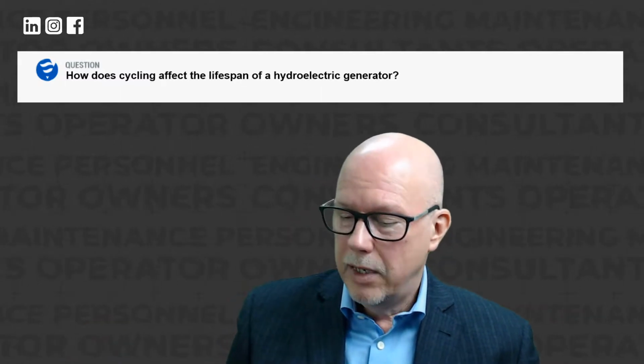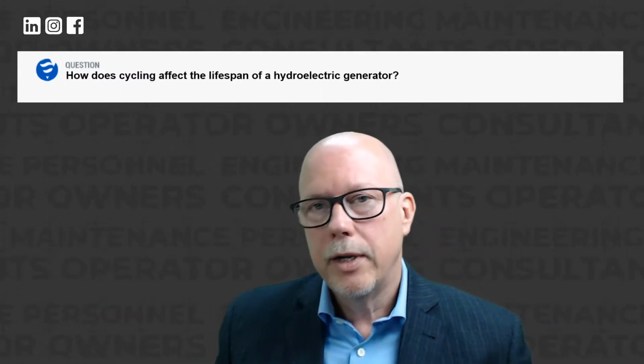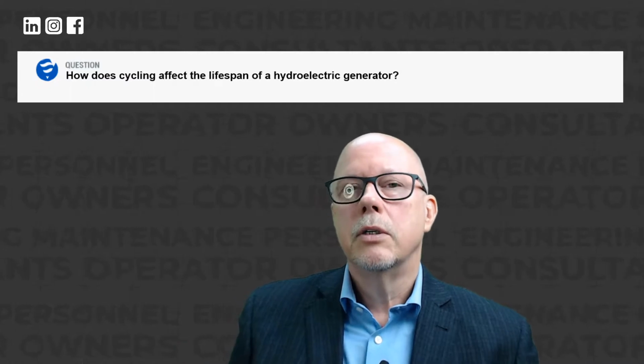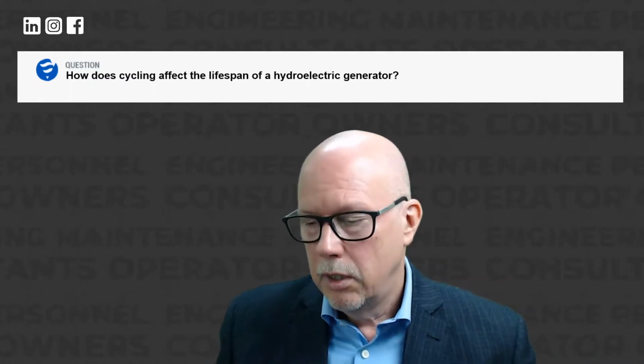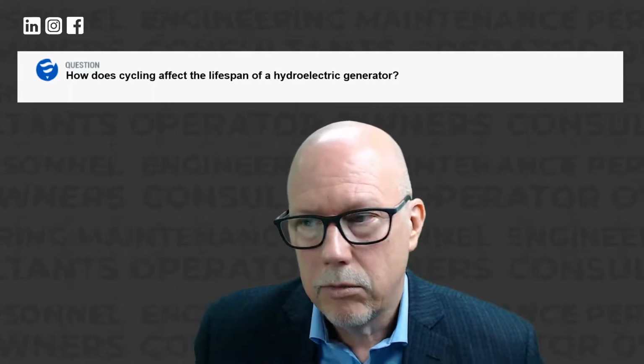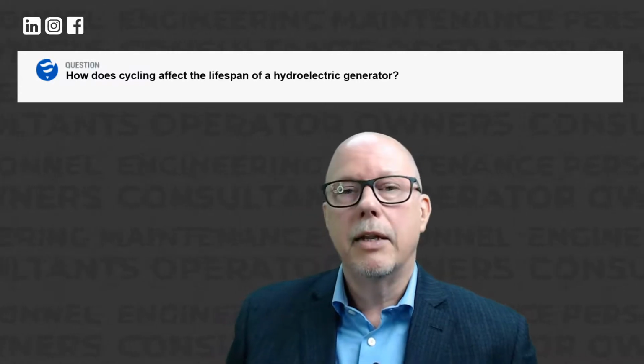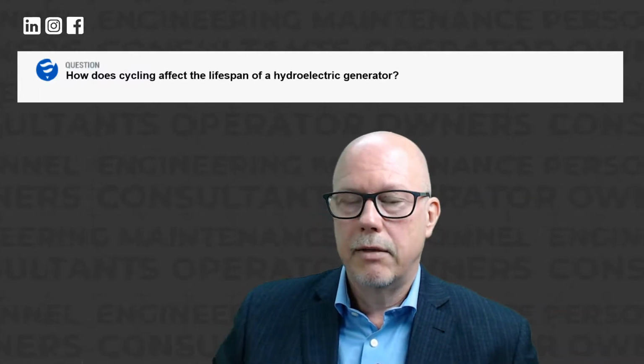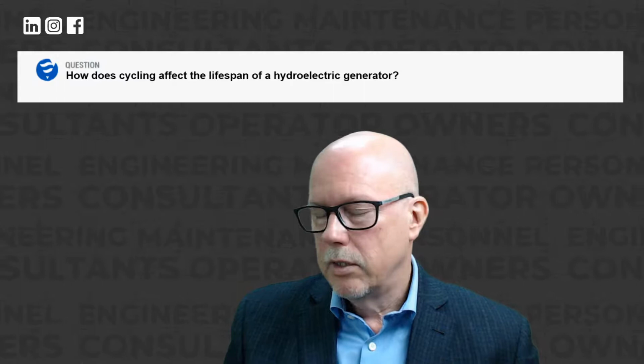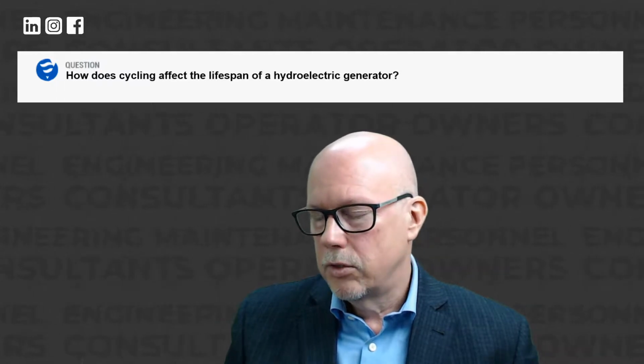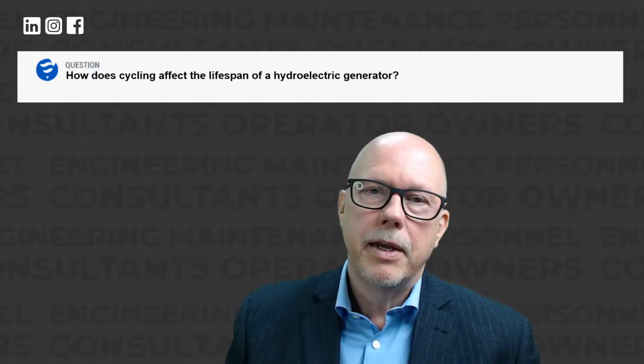Now, if you have a unit that's been operating as a base load unit for 20 years and damage has occurred, and then you start cycling the unit, that's even worse—that's really bad. That's probably the reason why we see a lot of insulation or winding failures. So the cycling definitely has an impact.